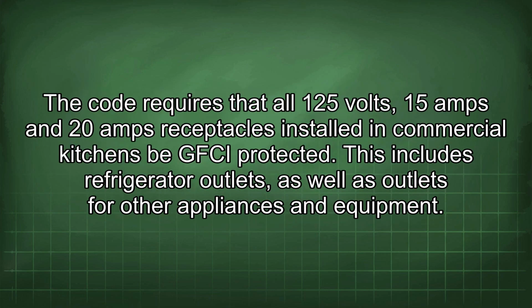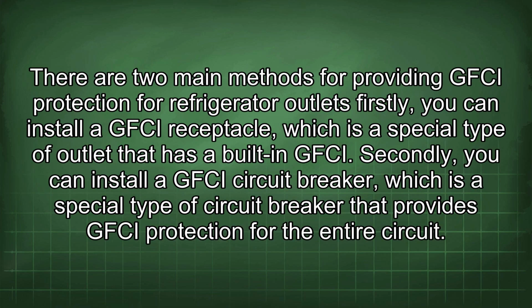The code requires that all 125 volt, 15 amp and 20 amp receptacles installed in commercial kitchens be GFCI protected. This includes refrigerator outlets, as well as outlets for other appliances and equipment. There are two main methods for providing GFCI protection for refrigerator outlets. Firstly, you can install a GFCI receptacle, which is a special type of outlet that has a built-in GFCI.